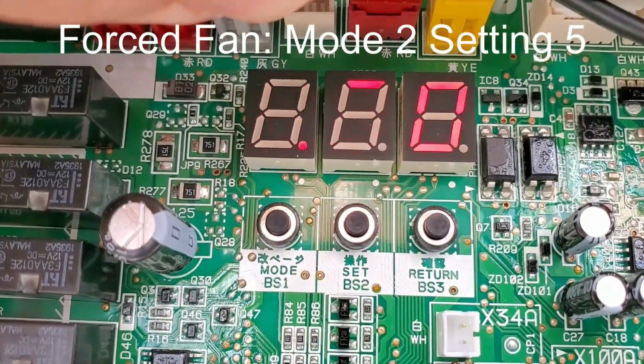Now leave it here, walk the job, look for the problem child indoor unit or indoor units. Great, we found them. Go back to the outdoor unit, turn it off. Fix the problem, come back to the outdoor unit, turn it on, press and hold return for 20 seconds to tell this outdoor unit or this type of board to readdress the indoor units, because we are now adding to the number of indoor units on the communication circuit.